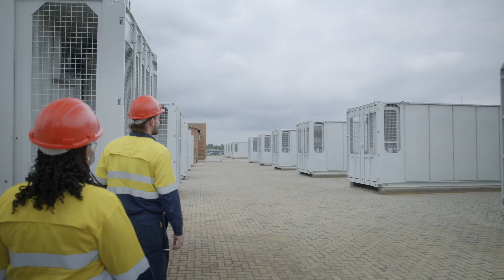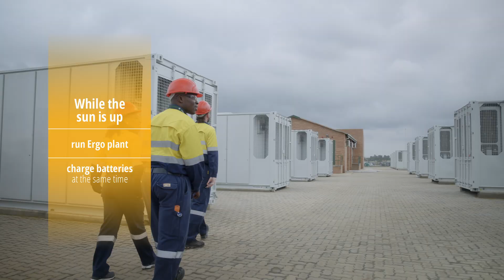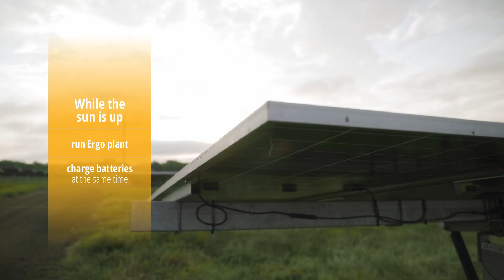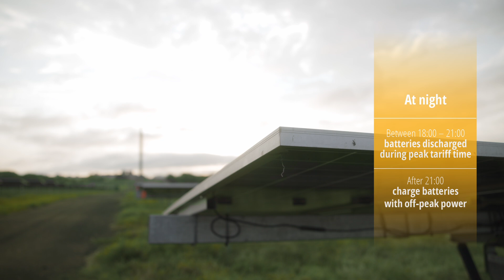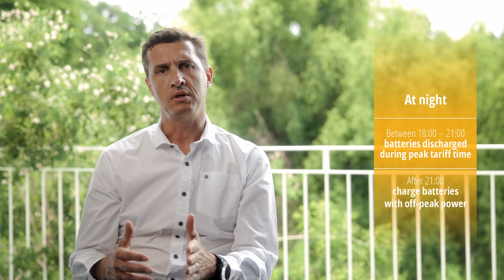The idea is to run the circuit where you start up in the morning, on peak period, off the batteries. Once the sun is up, the solar takes over and the plant runs off solar, while also charging the batteries from the solar. Going into night time between 6 and 9, you discharge the batteries again during that peak period, and after 9pm you charge the batteries with off-peak power from the grid.